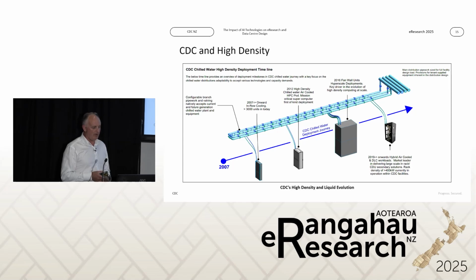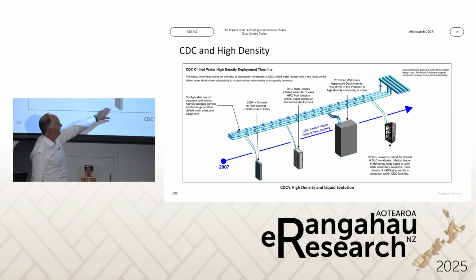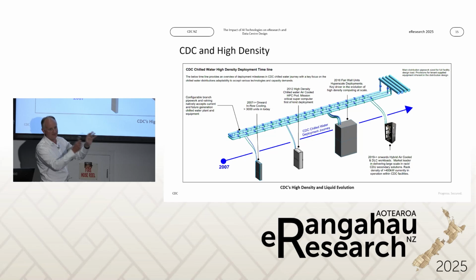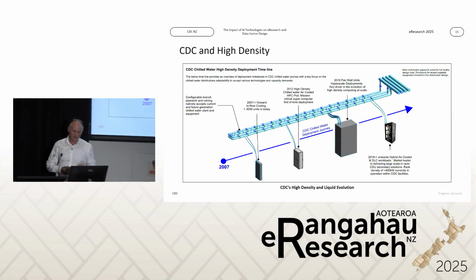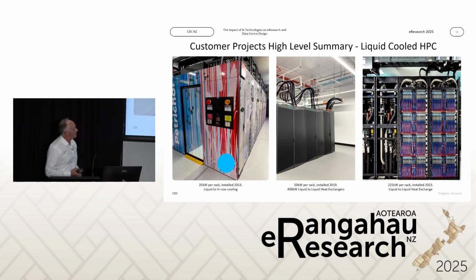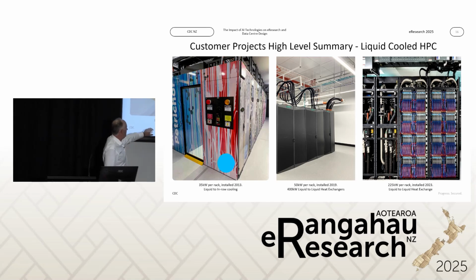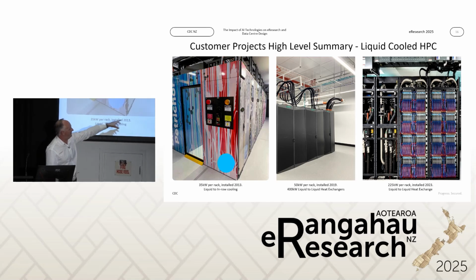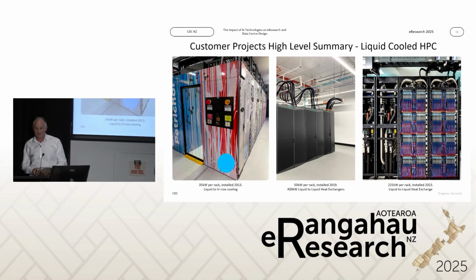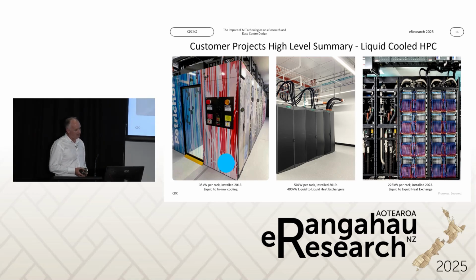And we've been on this journey for a long time. All the way back in 2007, we made a decision to use chilled water as our heat rejection methodology, and all of our buildings have this as their lifeblood pumping through the data center. We've been doing essentially almost liquid-based cooling all the way back then. We've got 3,000 in-row cooling units installed across Australia and New Zealand, and we've just been adding on and plugging into this fungible chilled water backplane for many years, right through to this next generation. Here's a few projects of our sites: all the way back in 2013, 35 kilowatts a rack with in-row cooling, 50 kilowatts a rack in 2019, and more recently we've been doing deployments in Australia for supercomputing in this space here.